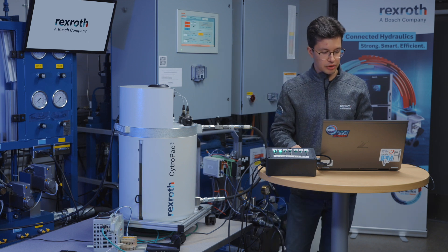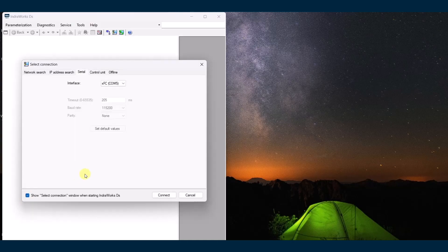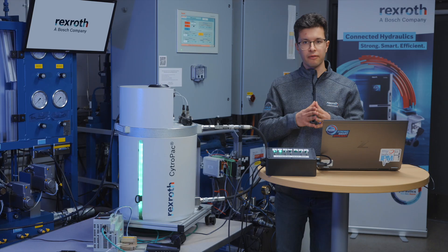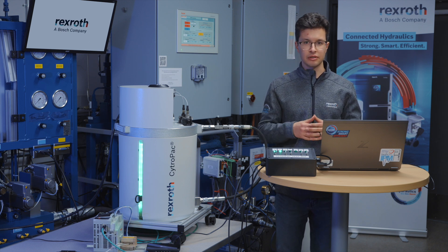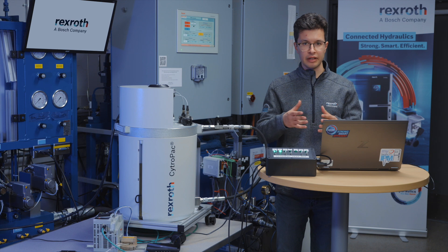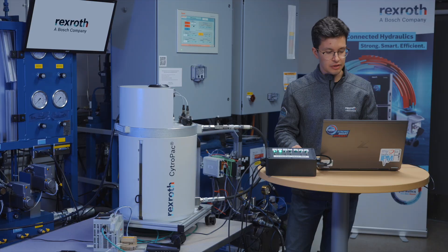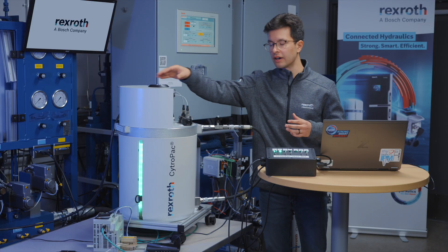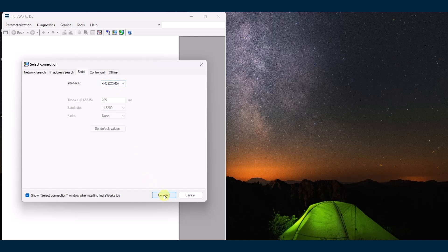Now I'm going to go through IndraWorks DS and show you how to plug in and start it up. IndraWorks DS is a free software available on the Bosch Rexroth website — see the link in the description below to install it on your PC. When we first open up IndraWorks DS, we're prompted to select connection. You're going to be under serial interface, and your interface you're going to be looking for XFC, which is the variable frequency drive built inside every single CytroPac. Once you see this in your interface, you click connect.